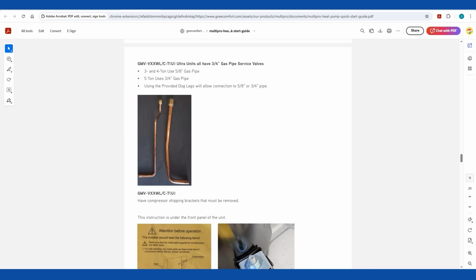But on 3, 4, and 5 ton, I just want to pass this out to everybody: make sure you know the service valves on all 3 of those units, 3, 4, and 5 ton, are all 3/4. So if you're doing 3 ton or 4 ton, that uses a 5/8 gas pipe. Use these dog legs that come with it, or another adapter if you want. This is already flared for you, and your 5/8 pipe will slide right into that dog leg, and you can braze it right there. These actually turn pretty nicely to go out through the unit anyway, and might save you some bending pipe.